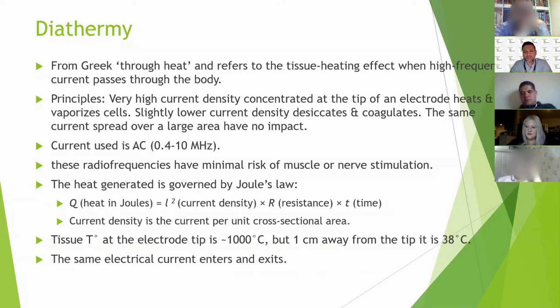And that's why it's very important for monopolar to have a bigger surface of receiver and make sure that there is no obstruction, nothing blocking it. Okay. Now, the current is alternating current, AC, and it has 0.4 to 10 megahertz. These radio frequencies do not affect the muscles or nerves, so they do not cause twitching of the muscles or the nerves. You have to have way lower frequencies than that to affect the nerves.